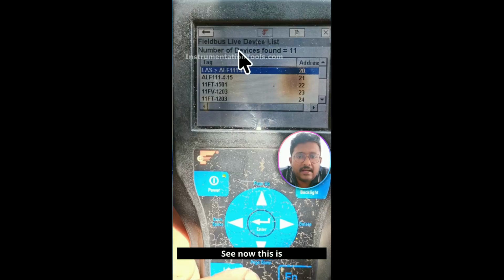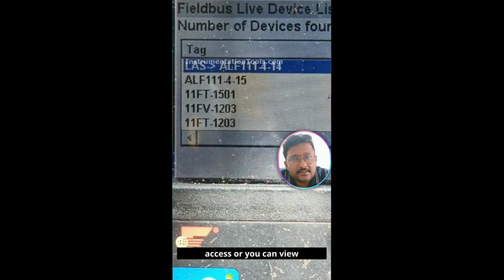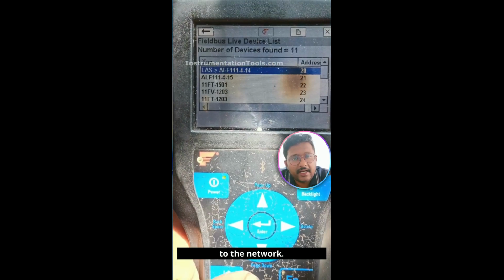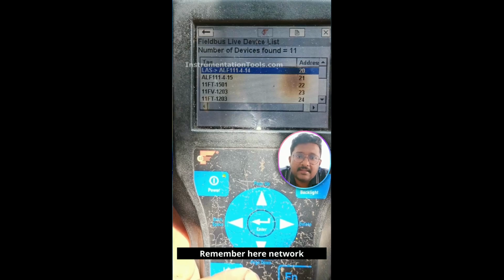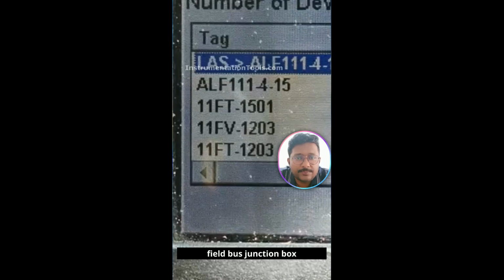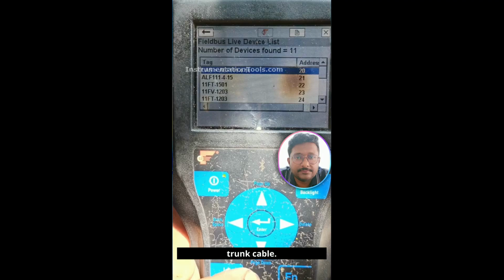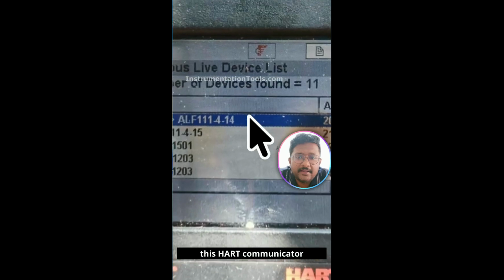See, now this is the live list. Okay. Fieldbus live device list. When you connect your HART communicator to any instrument, you can access or view all devices connected to the network. Remember, here network means the respective foundation fieldbus segment or foundation fieldbus junction box or foundation fieldbus trunk cable. Let's say there are 30 foundation fieldbus junction boxes. That means you have 30 networks, 30 segments. So when you connect your HART communicator to your field instrument, you can access the devices related to a single segment. Now we will see this HART communicator's details.